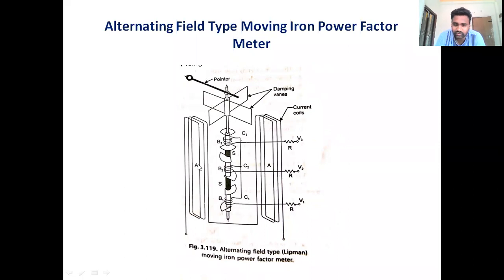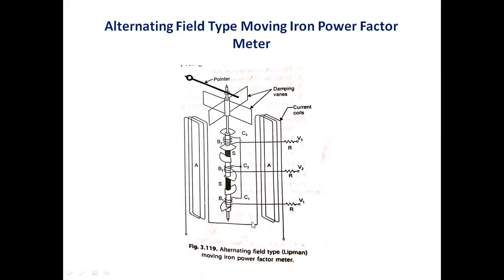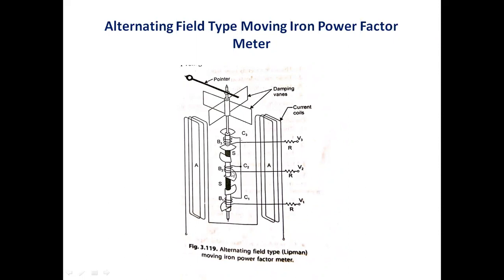The current coils — elements A — are split into two halves. One half is on the first side of the moving system and one on the second side of the pressure coil system. The spindle of the moving system is connected to the damping vanes and also to the pointer.